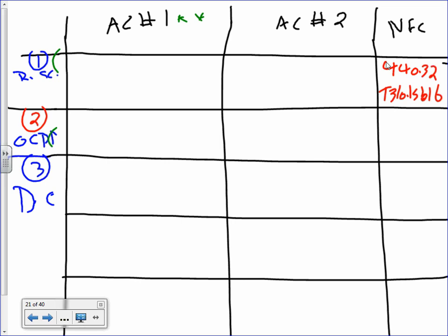If you go to 440.32, it tells you, by the way, it's continuous load multiplied by 1.25. Really, no rocket science in it. So 1.25 times that full load amp. Now, there is no horsepower. There's no horsepower, is there? Nothing. So you're going to find the full load current, which is 70, right? Is it 70 for that one?